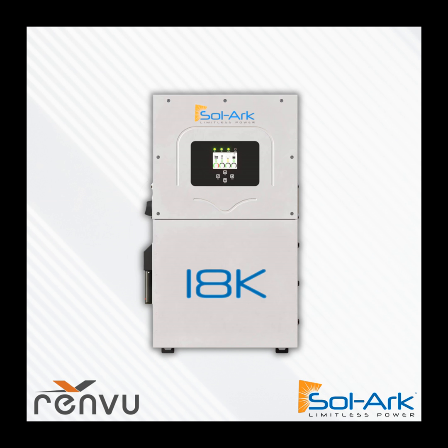If you like using Enphase microinverters, you can do that with a Sol-Ark system. You can interconnect your Enphase subpanel onto the gen port for AC coupled solar. Or if your solar array already exists and your residential customers want to hit that tax credit one more time before it goes away next year at the residential level, you could take an existing batteryless solar array and AC couple it to a Sol-Ark on that gen port for a very easy installation.